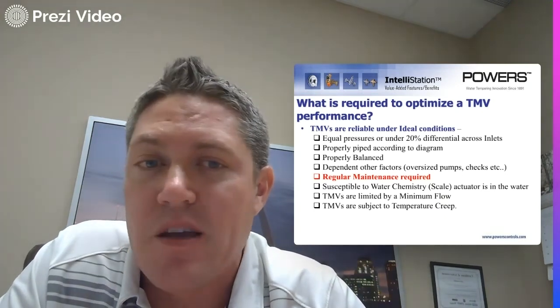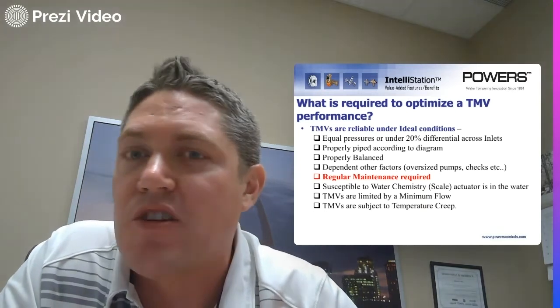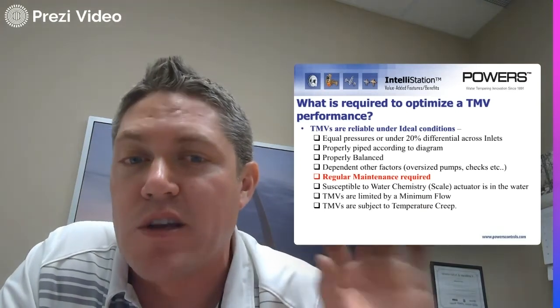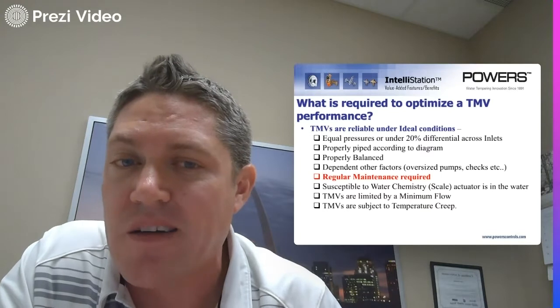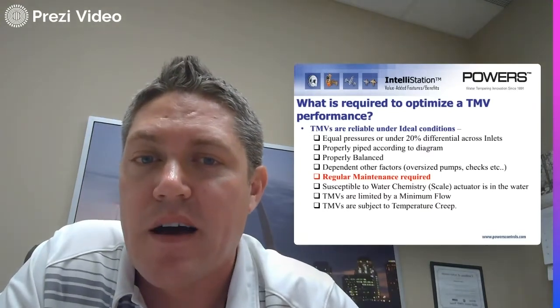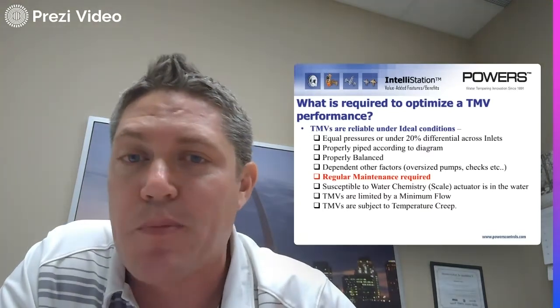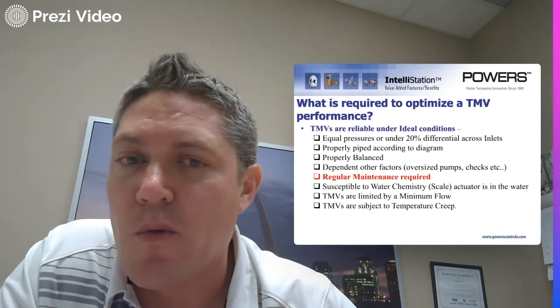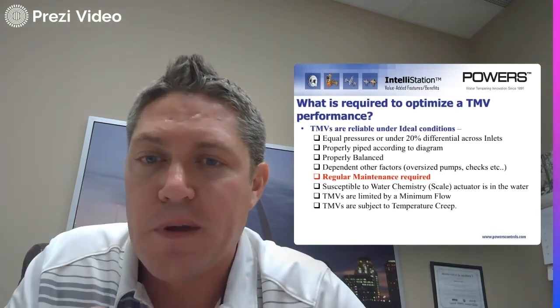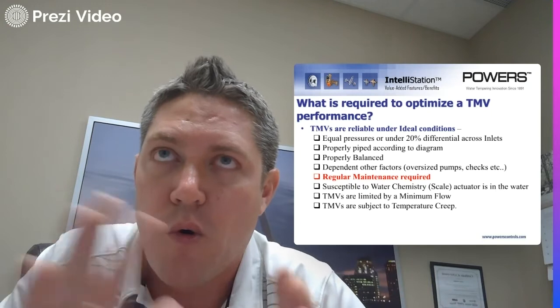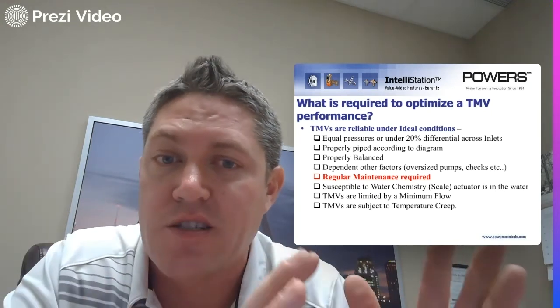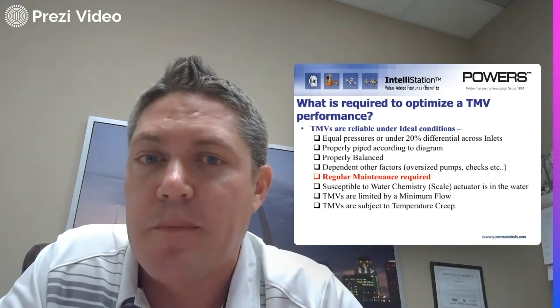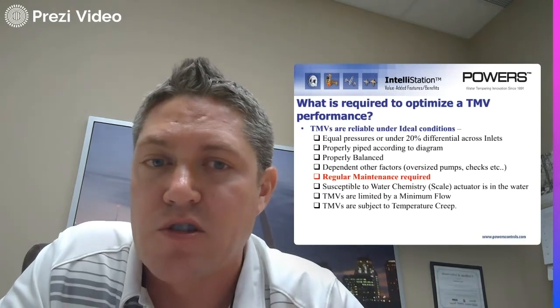It needs to be properly piped to a diagram. That means all the checks in the right spot, the return pump in the right spot, the balancing valve in the right spot, which brings me to the next point. It needs to be properly balanced. We'll talk more about this, but open loop versus closed loop, or flow versus just recirc. Same thing, open loop, closed loop.